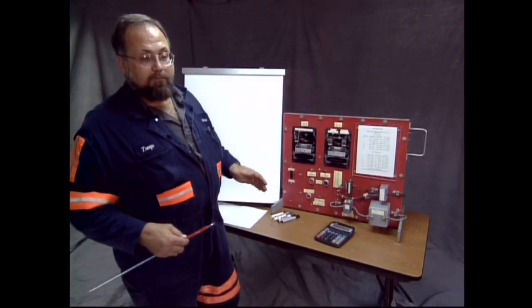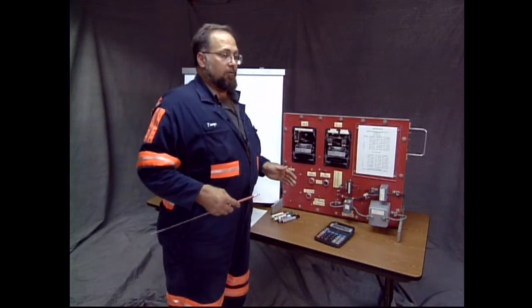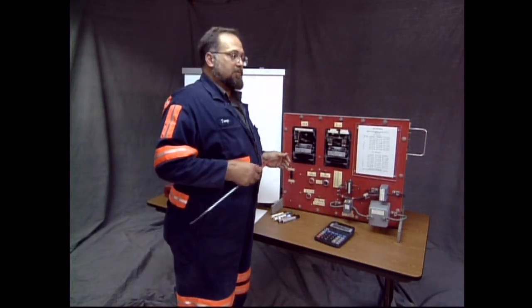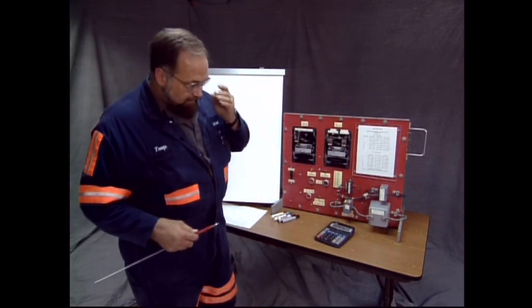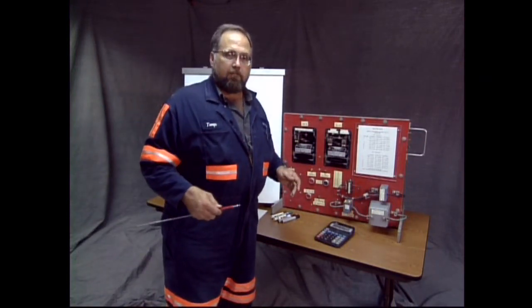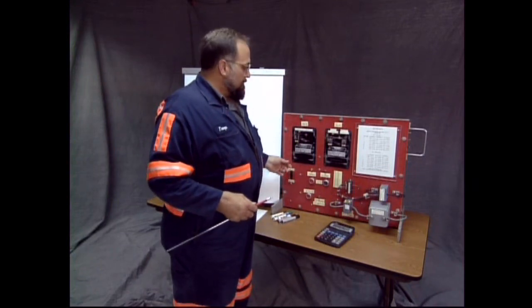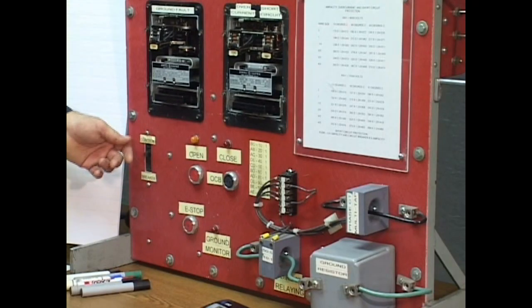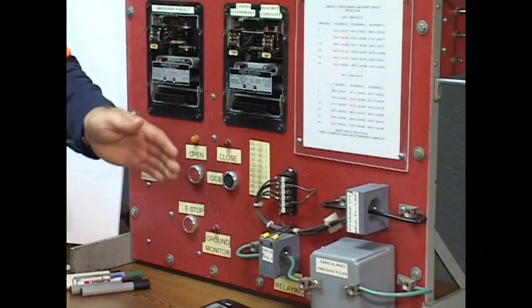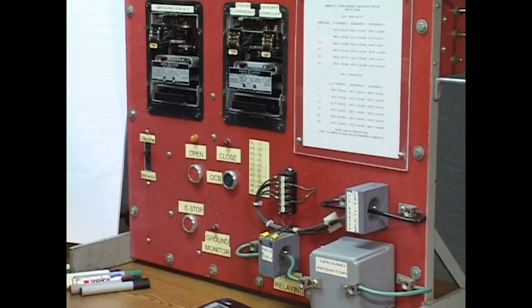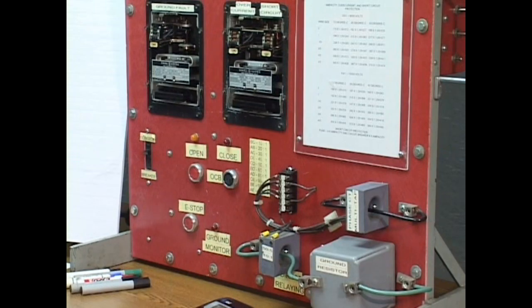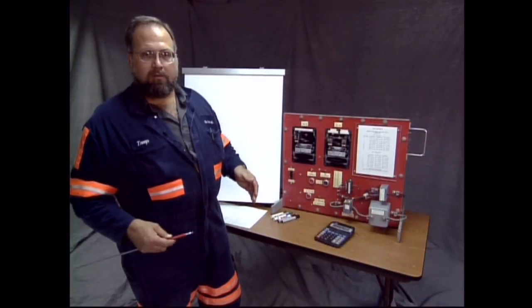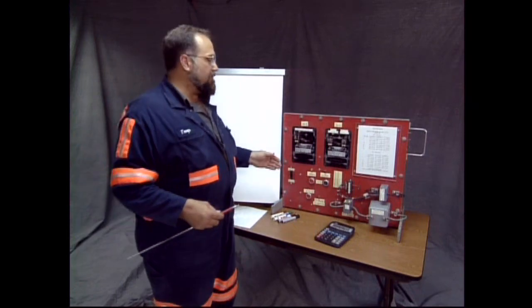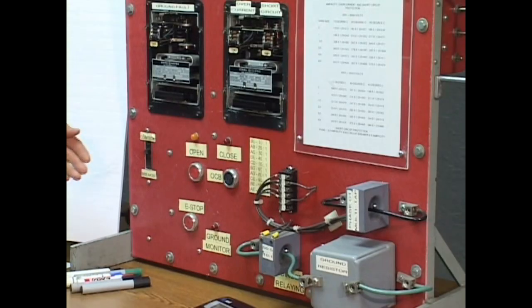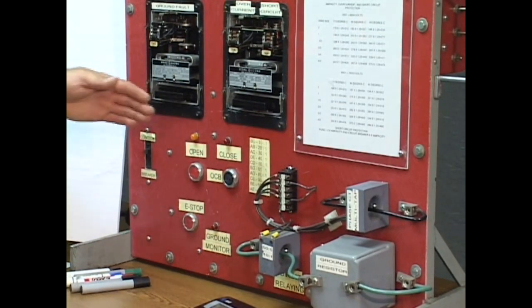So people confuse the control breaker, thinking that when you have an under voltage situation, it trips the control breaker. Indeed, you test the under voltage protection by operating the control breaker. To simulate a power outage, you will open the control breaker to take power off the relays. Your OCB should open, and it should remain open after power is restored. And that exhibits under voltage protection. But the breaker doesn't provide under voltage. It's a thermal only breaker, similar to one you would find in your load center at your home. It's just to protect the wiring here.